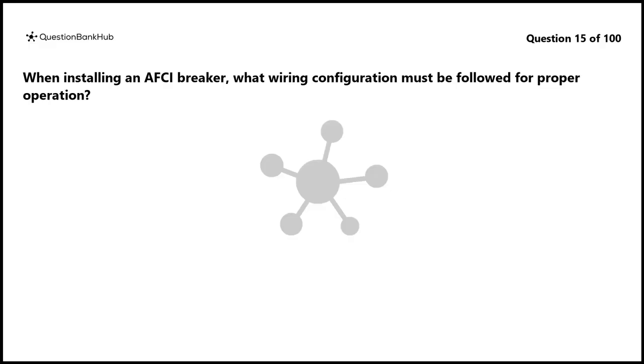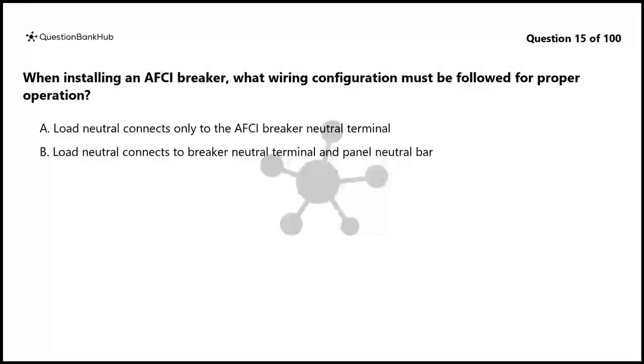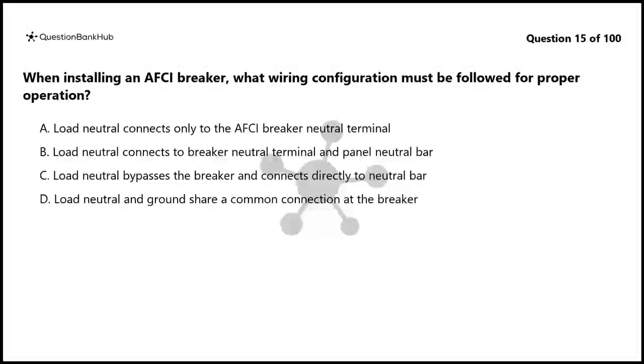Question 15. When installing an AFCI breaker, what wiring configuration must be followed for proper operation? A. Load neutral connects only to the AFCI breaker neutral terminal. B. Load neutral connects to breaker neutral terminal and panel neutral bar. C. Load neutral bypasses the breaker and connects directly to neutral bar. D. Load neutral and ground share a common connection at the breaker.